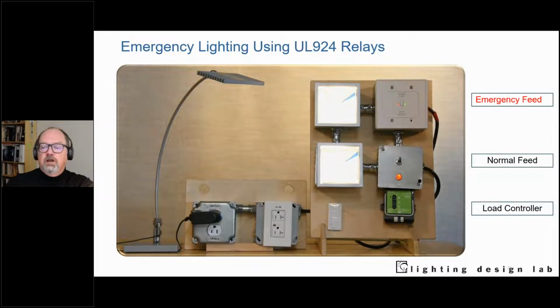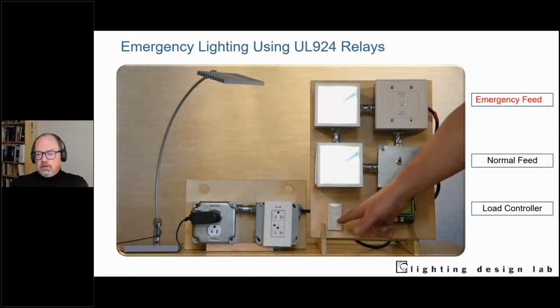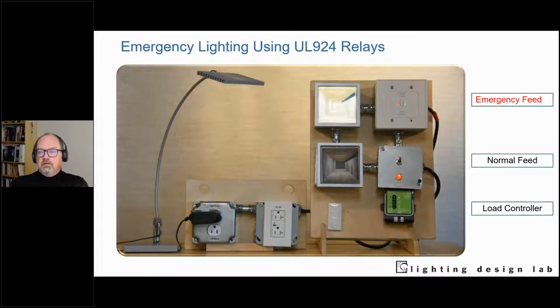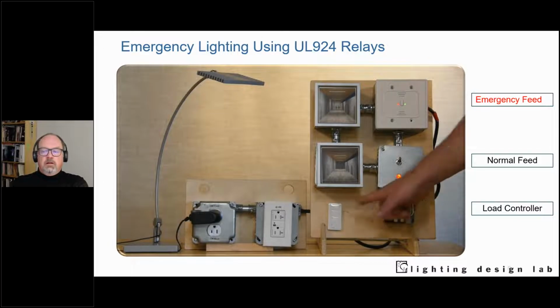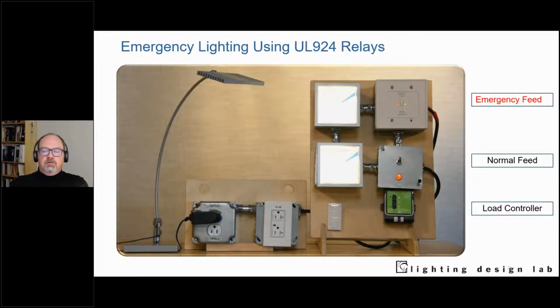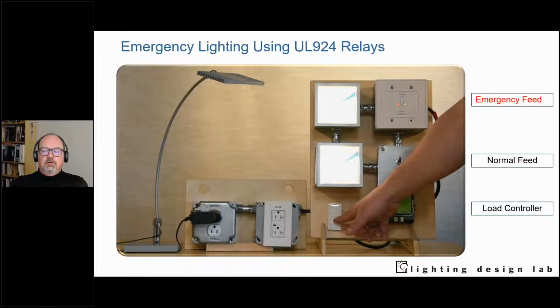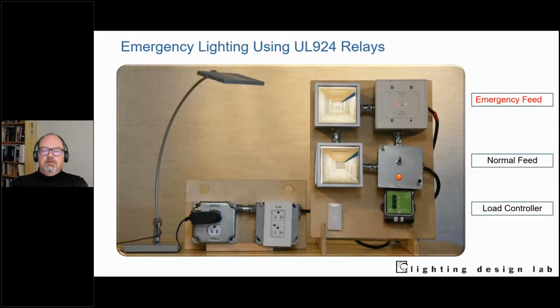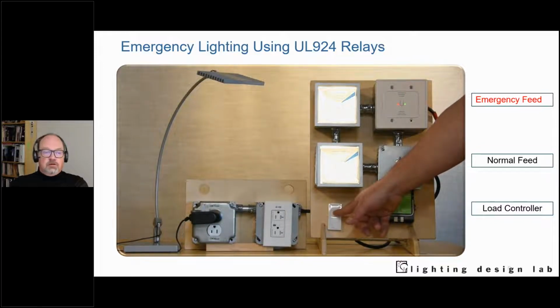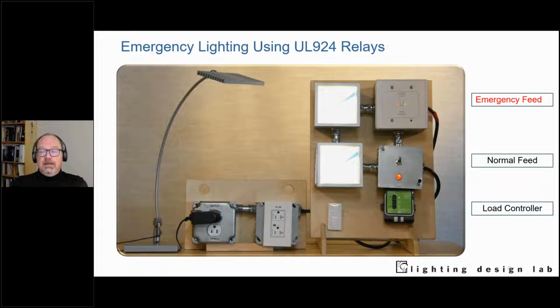So I'm turning the corridor lighting on, and now I'm turning it off. You'll notice it all goes off together. Now I'm going to turn it on and show you that I can dim both of them together, dim up, dim down if I want to. Now, if I lose normal power, you'll notice the emergency goes to full light output. And when I restore the normal feed, the system senses that and brings the light back to the level it had been at before, while still allowing me to dim up or dim down.